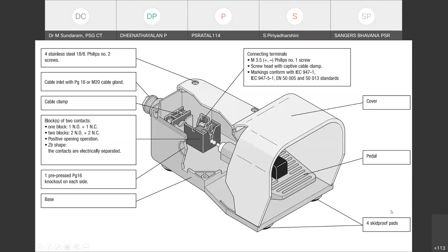In connection, there are two things we have to look at. One is current sinking, another is current source. What do you mean by sink and source? If you connect plus 24 volt as common, then it is going to be a sink. Minus will be connected here. That may be a two-wire loop or it may be a fully isolated loop.